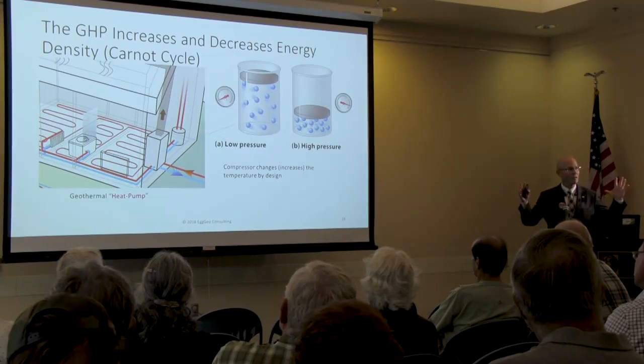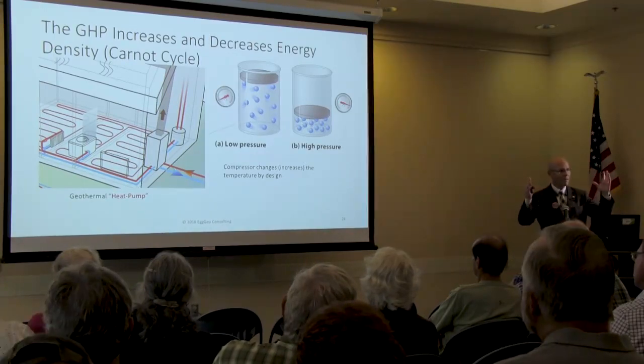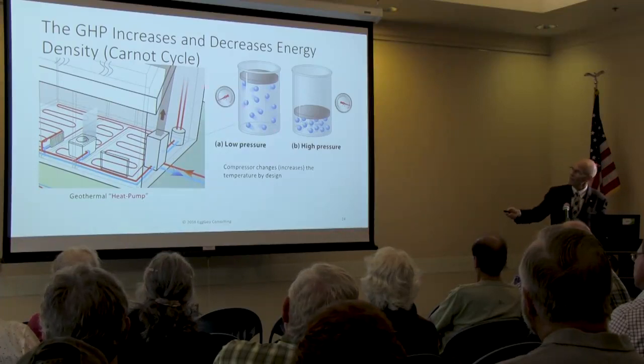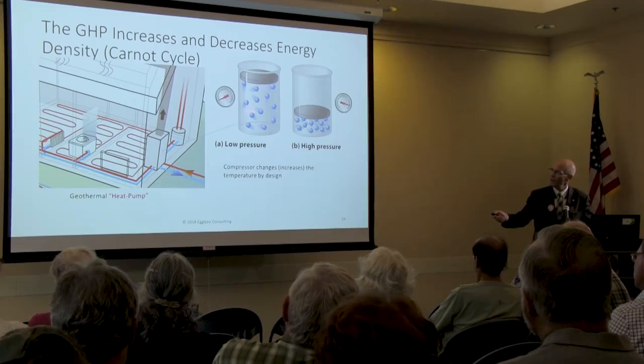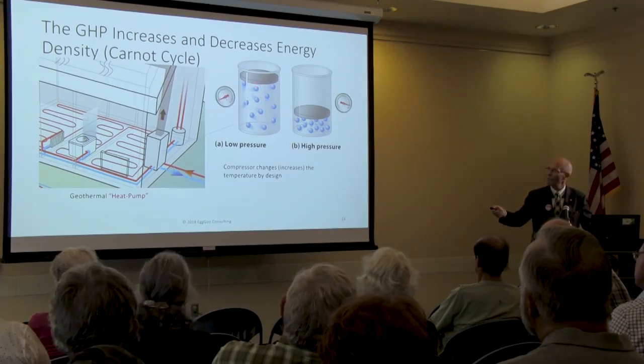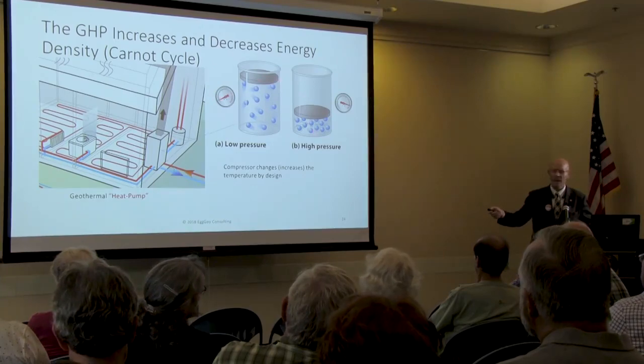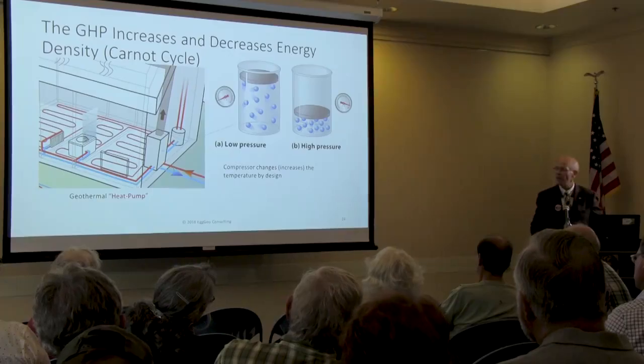And these are all the different ways that we can do that. Now, remember when I talked about the cubic foot of air in front of me? If you compress it down to 1/10 the size, this is kind of a graphic representation. Here is this volume of gas at a low temperature, and when you compress it, it's still the same gas, it's just at a high pressure and high temperature. This is because, in thermodynamics, heat only moves from a warmer temperature to a cooler temperature. So if we want to manipulate the heat available in the ground at 55 degrees, we just have to compress it, and that's what our heat pump is doing. It's actually pumping the heat up to a warmer temperature, but it's only using 1 kilowatt of energy to deliver 5 kilowatts of heat.